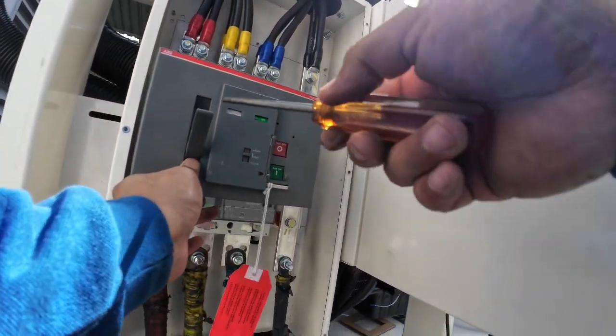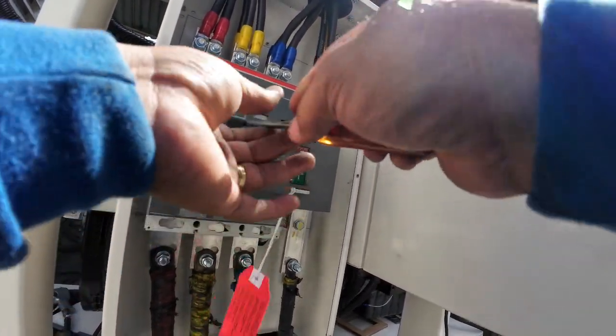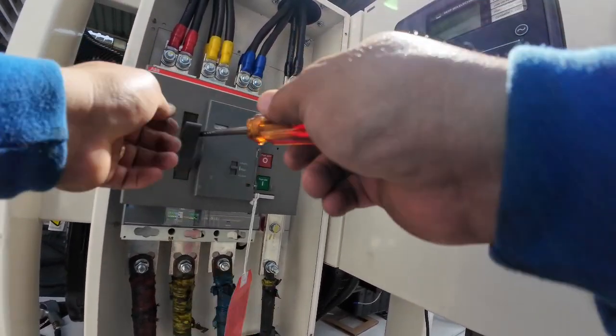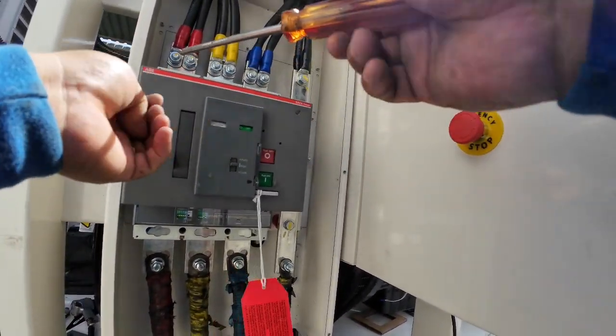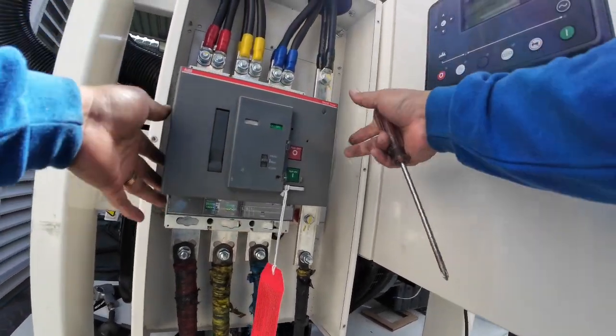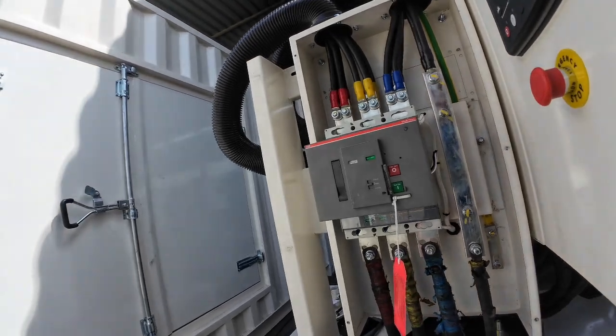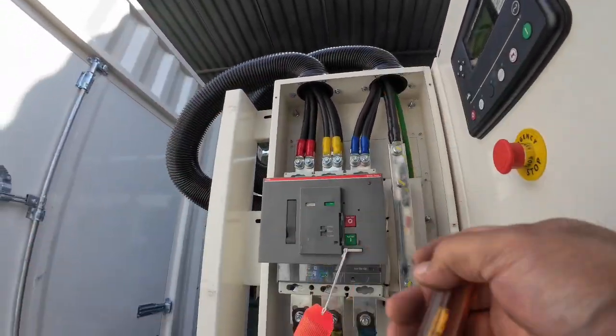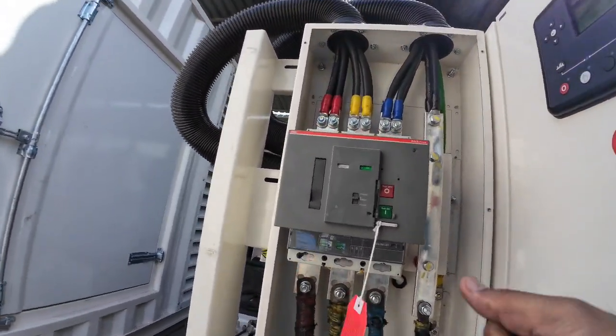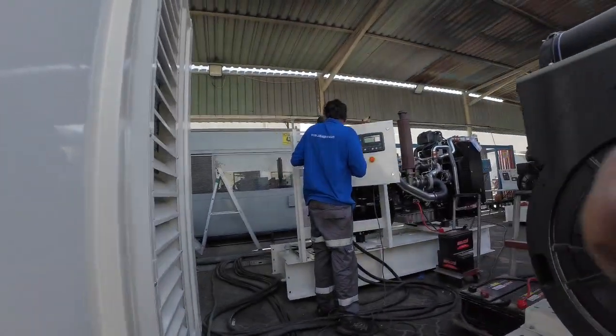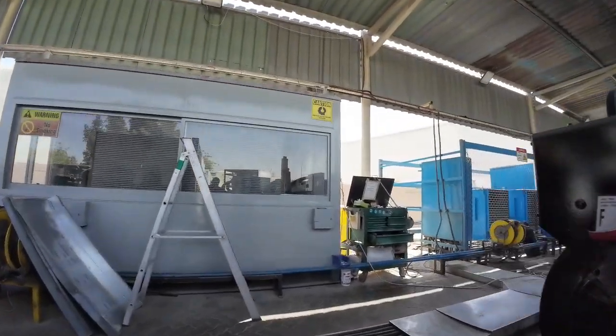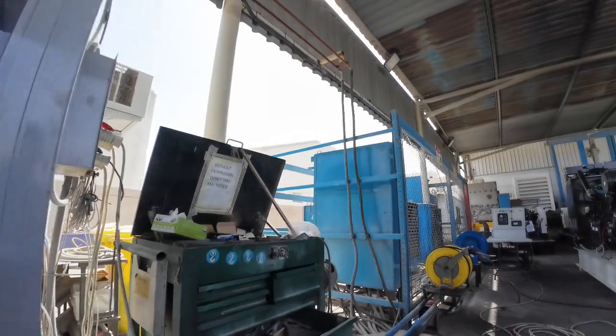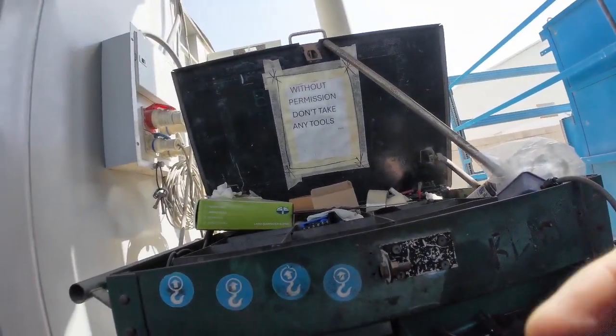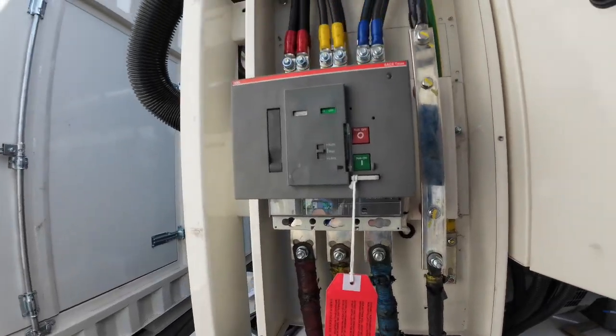So in here, I need to open the breaker because there is some problem. It is not closing properly, and it gives you a trip alarm, and it gives you bus not live. I will check the connections from inside and what the missing connections are. If there are any wrong connections, they should be fixed before finalizing and testing the synchros. It should be working properly, so we don't have any issue at all.